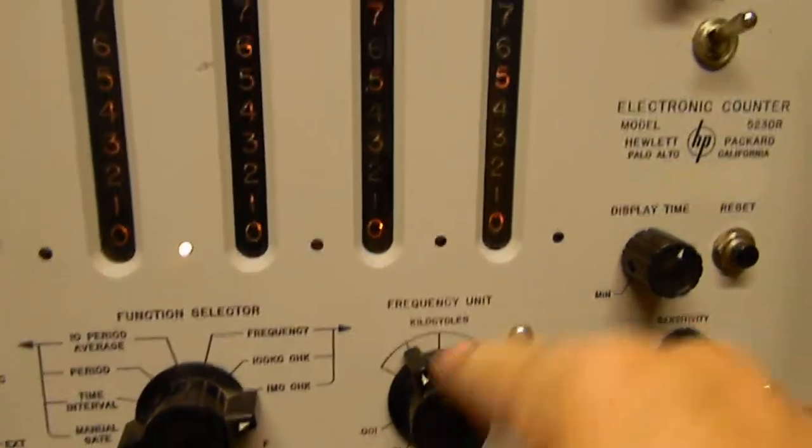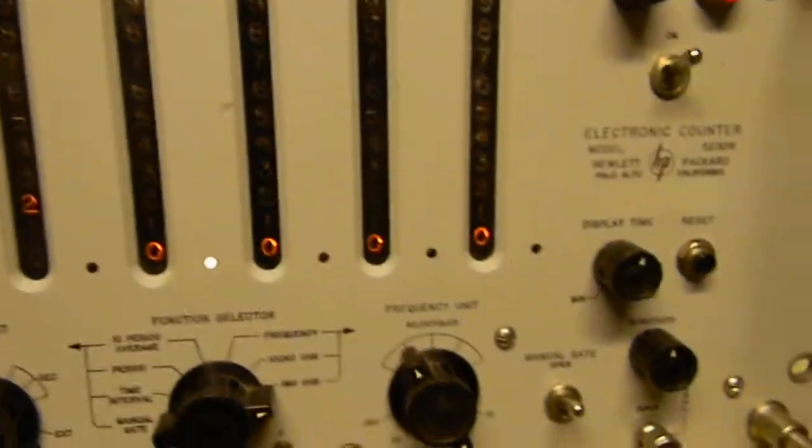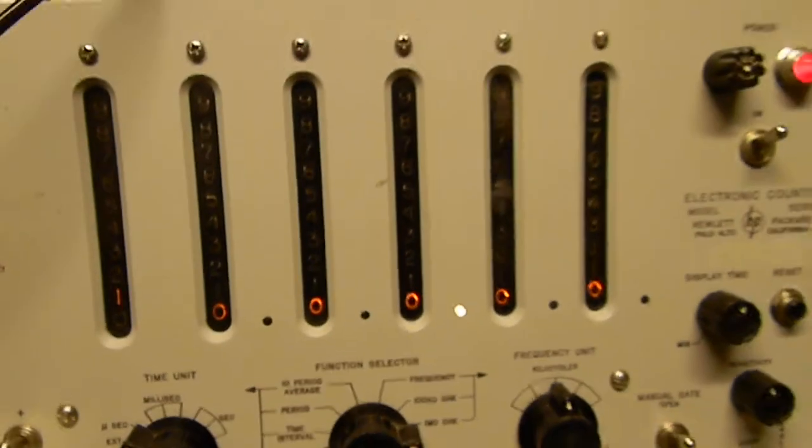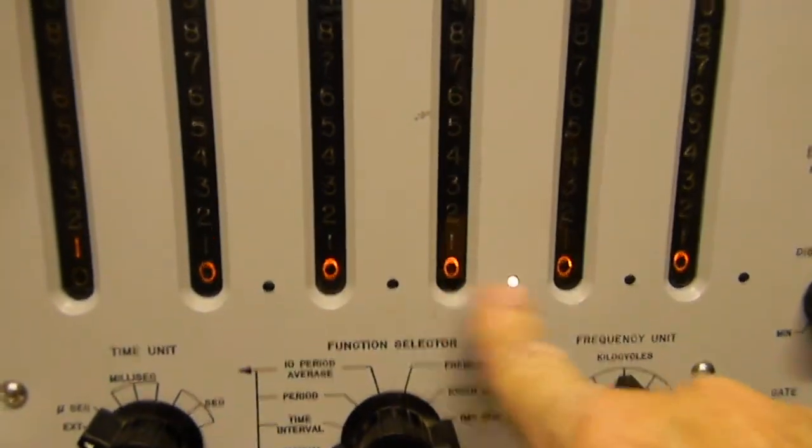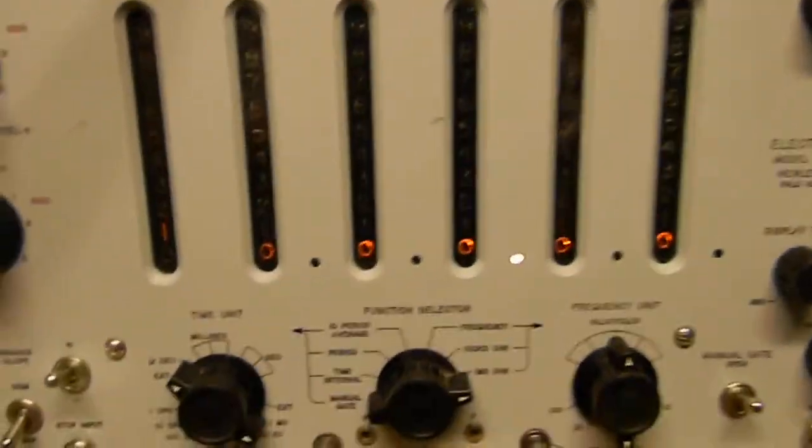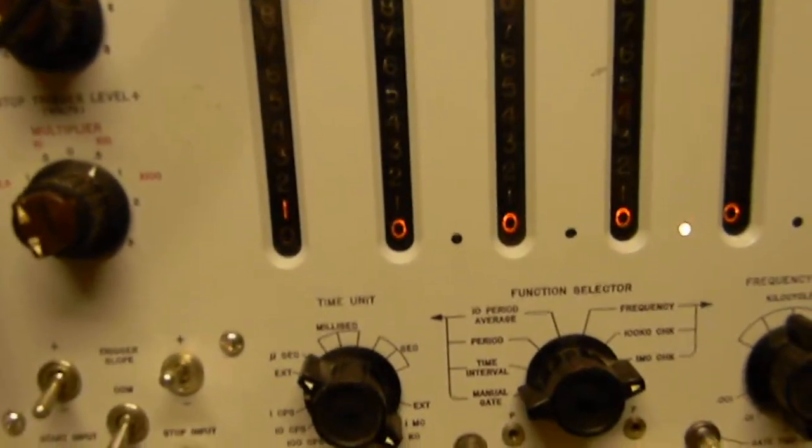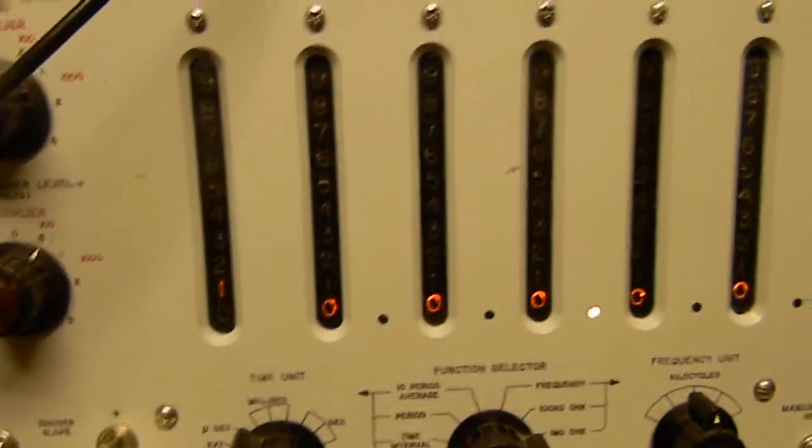If we put it in 1 megahertz, we have to move this to kilocycle. They didn't call it hertz back then, I guess. Everybody assumed that it was kilocycle per second. But there we go. Now we've got 1000.00 kilohertz, which is our megahertz cal signal.